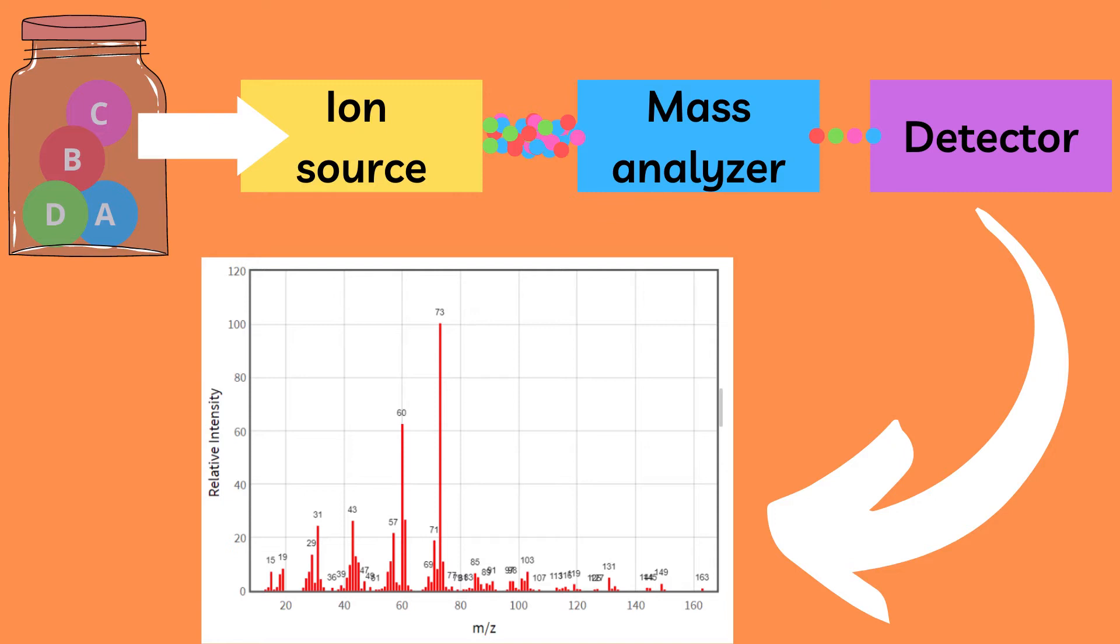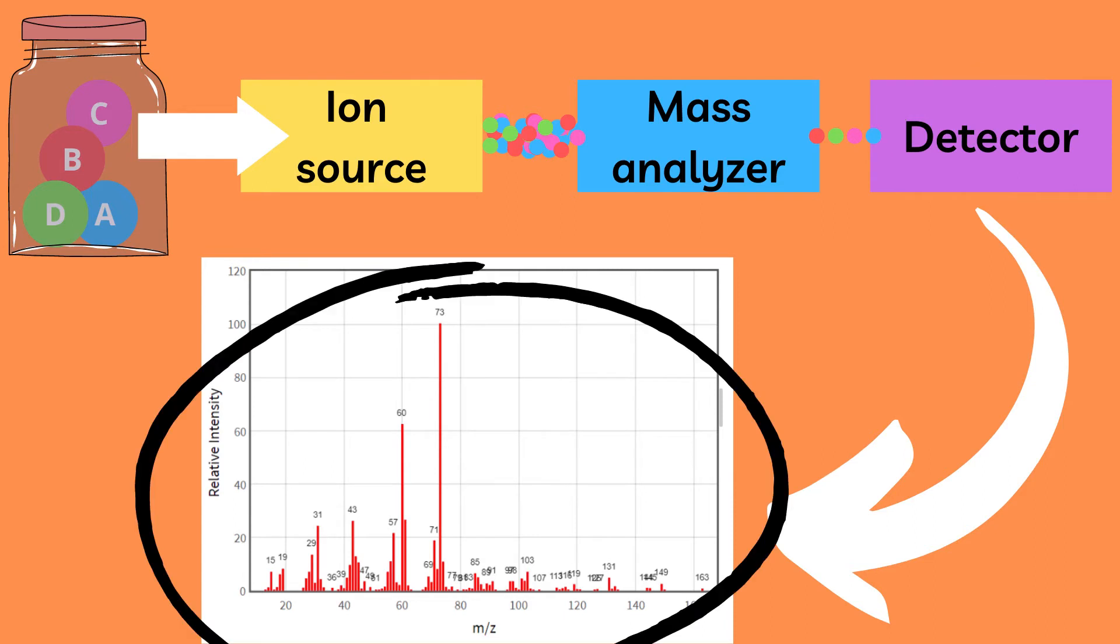Broadly speaking, the three major components of any mass spectrometry device are: one, an ion source which ionizes the sample; two, a mass analyzer that measures the mass-to-charge ratio; and three, a detector which converts the detected ions into a digital output.